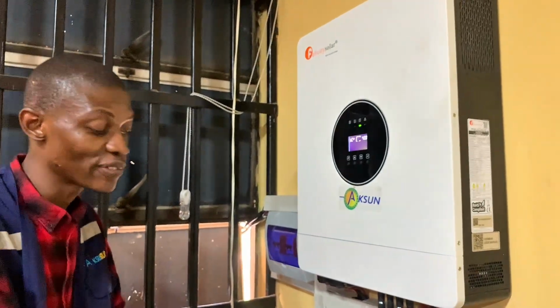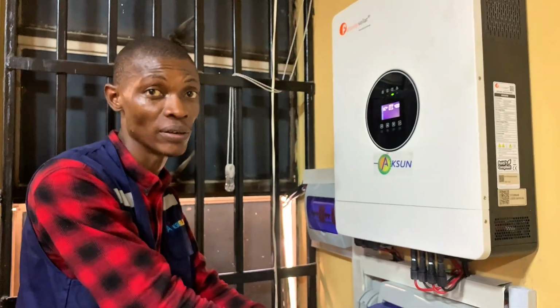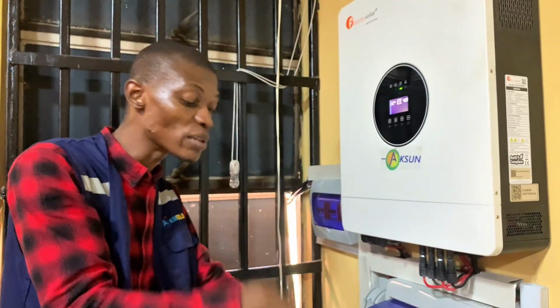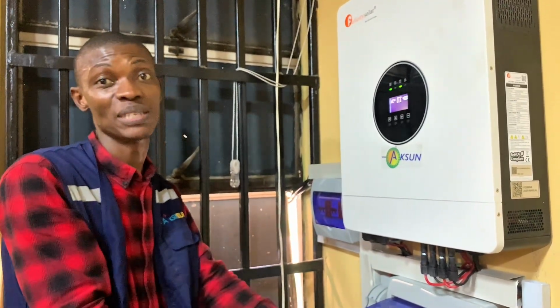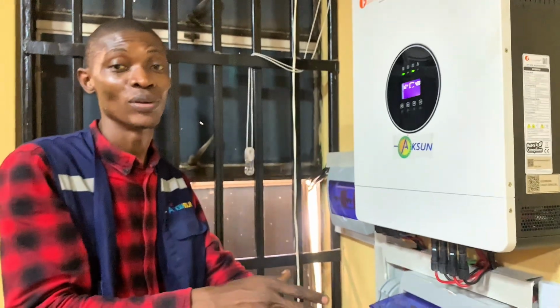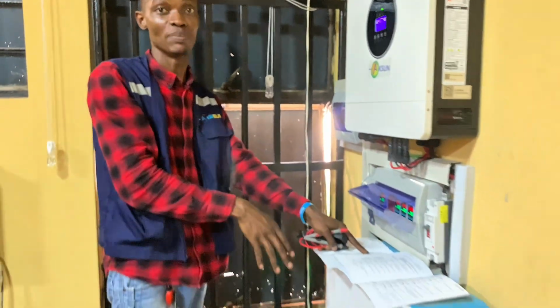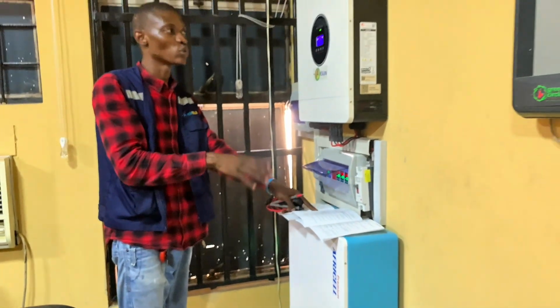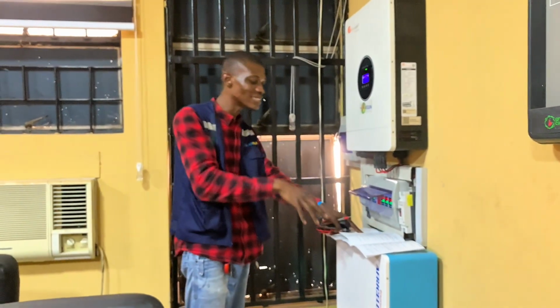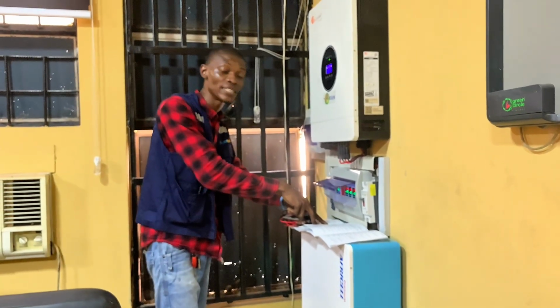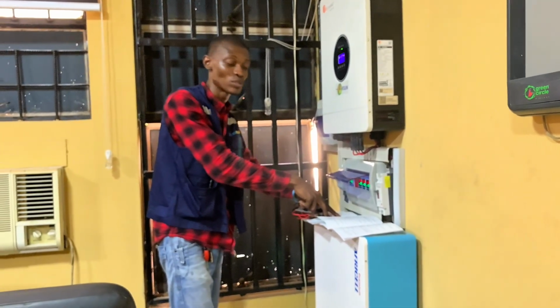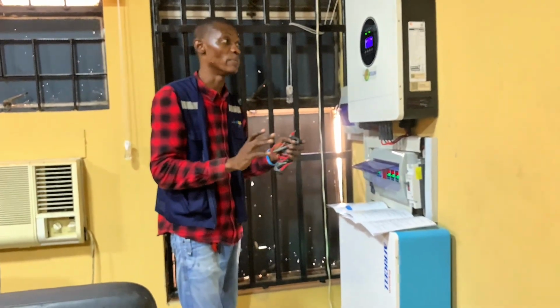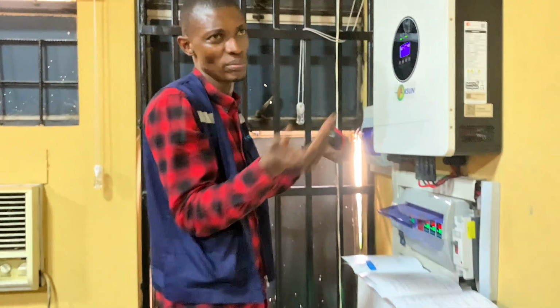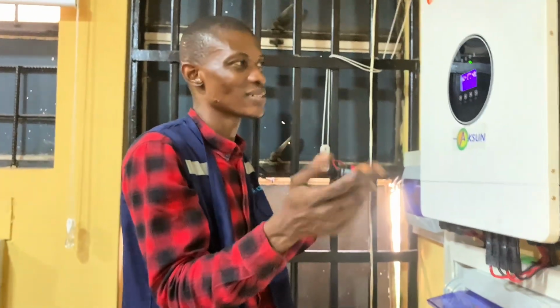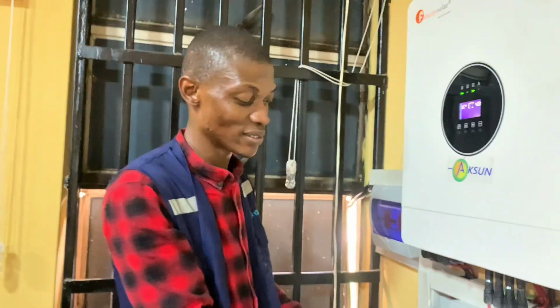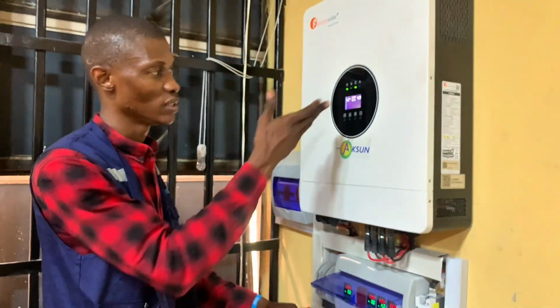If I'm shutting down exactly at 40 volts, the same level the manufacturer recommends, that means I'm shutting down at the same level the BMS of the battery is set to shut down, which can affect the BMS. There are some batteries that once the BMS shuts down, to recover you have to boost charge the battery for the BMS to recover back. So it's always said you don't shut down at exactly the recommended voltage, so as not to have issues with your BMS. Some installers might give 4 volts clearance, but I think if my brand's designer says 40 volts, 42 volts is okay.